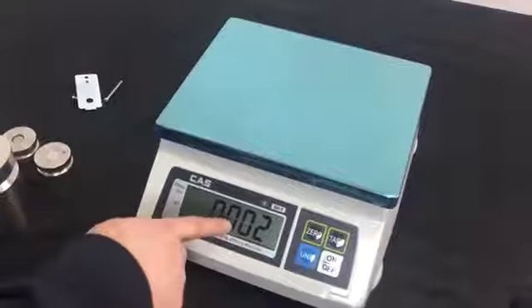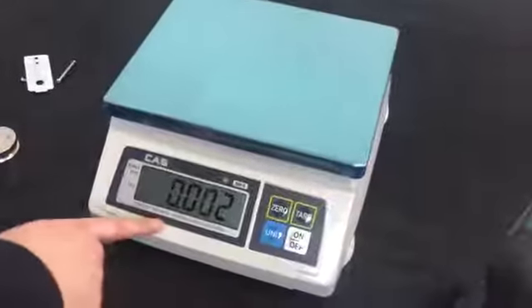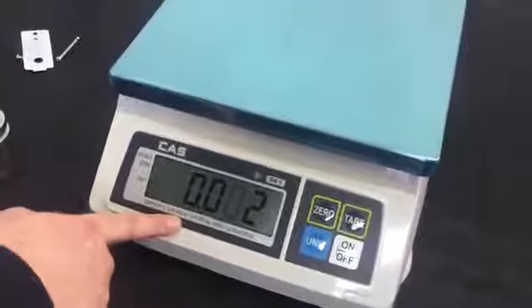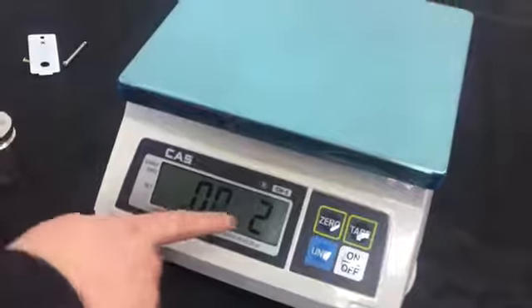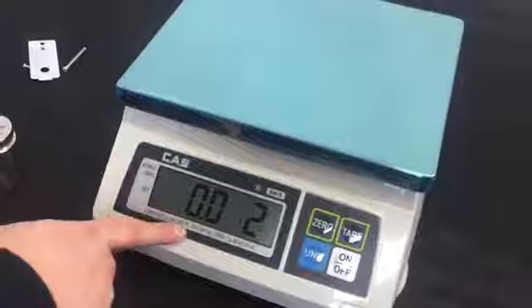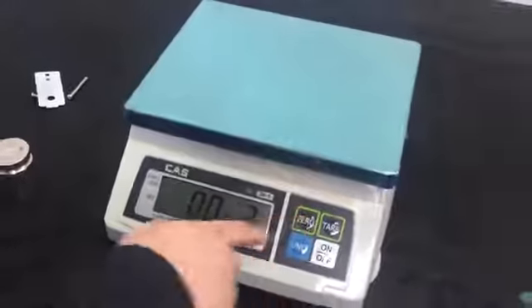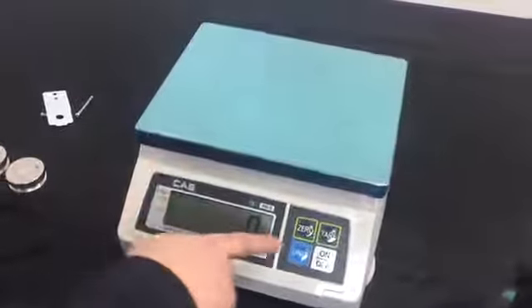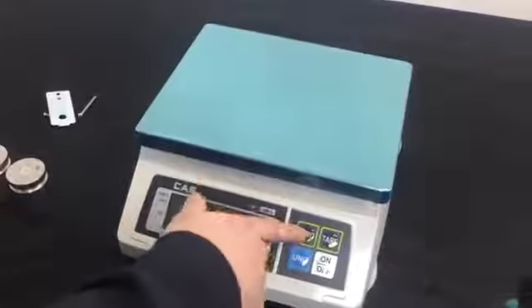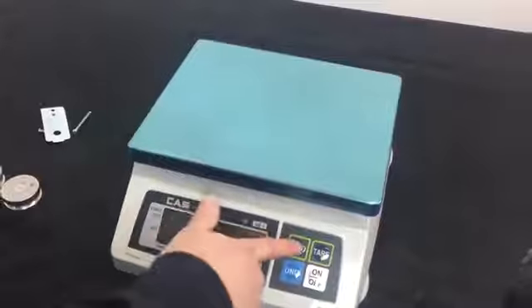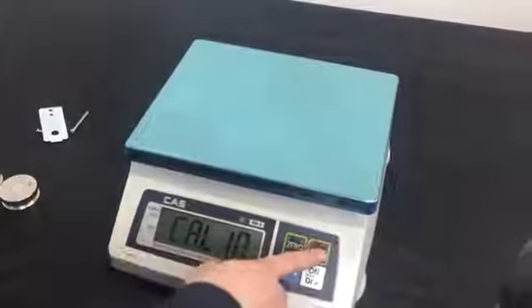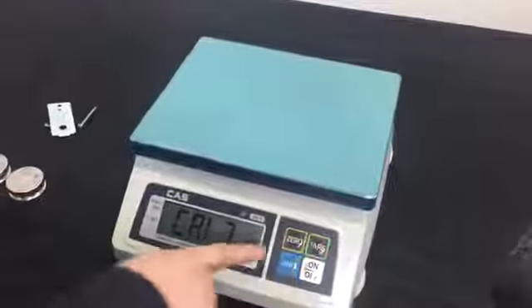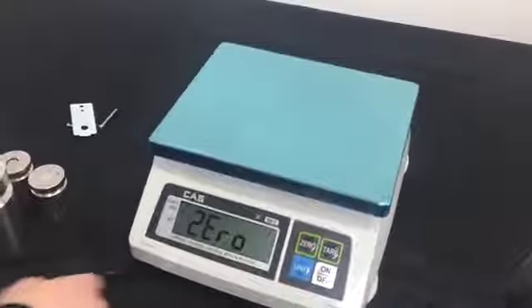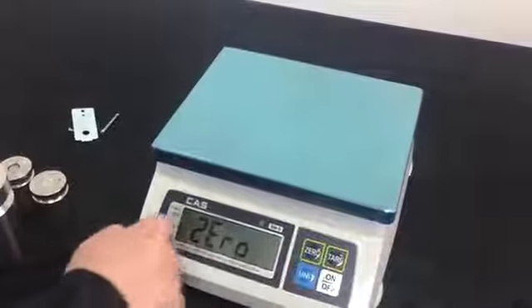1D shows the division, which is 0.002, as I showed on the capacity for the previous menu. This is correct. You want to make sure that this is matching up with your division. So as soon as that's good, you press the 0 key. Dual, this is not a dual range scale, so 0 is good. Press that. Tare, not using that, so 0 is good. Press 0, back to Cal 10. Now we're going to navigate to Cal 3. This is our actual calibration setting. So 0 in order to enter in.